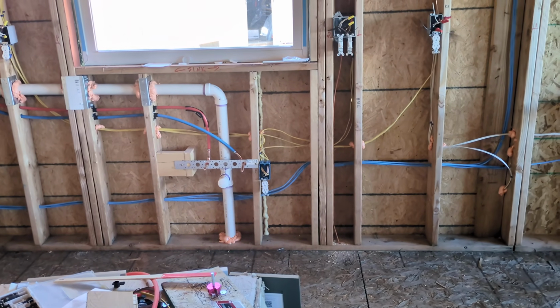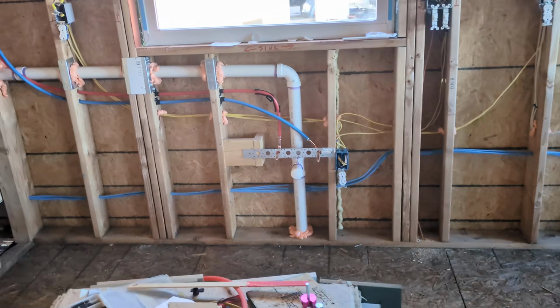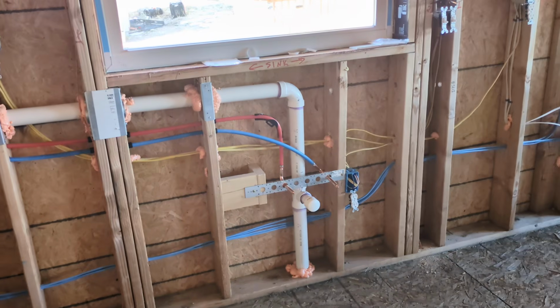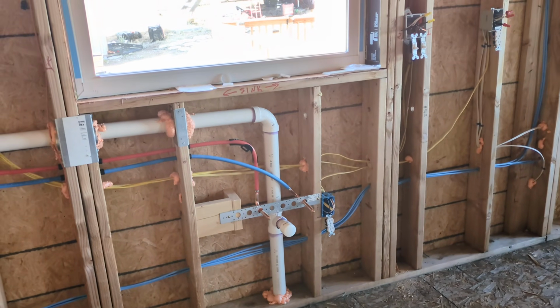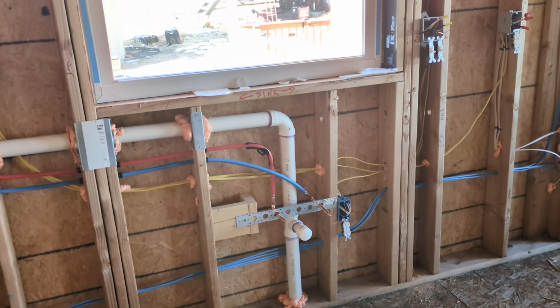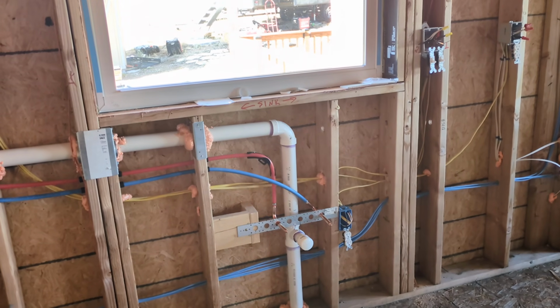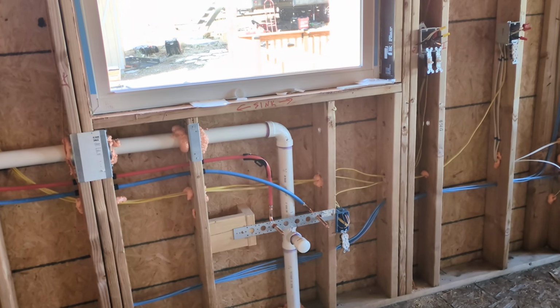First things first, on the kitchen side here, they're requiring us to have an air admittance valve. The reason for this was a little interesting. It was something I missed in the code, and I think it's easy for others to miss as well. The issue is that the vent needs to be above the flood level of the sink, the flood level of any item. Another mistake that I made was exactly the same one with the toilets, and I'll show you that in a minute.